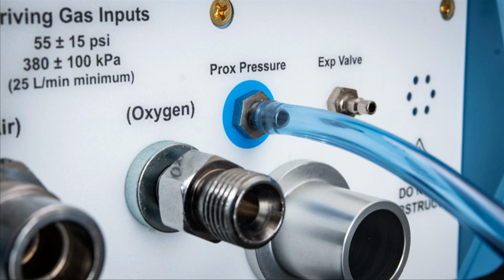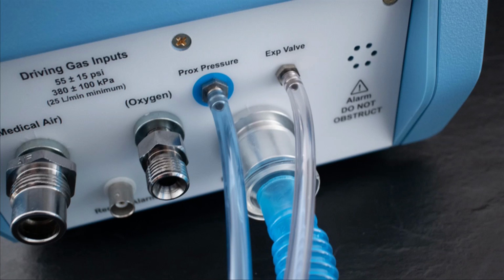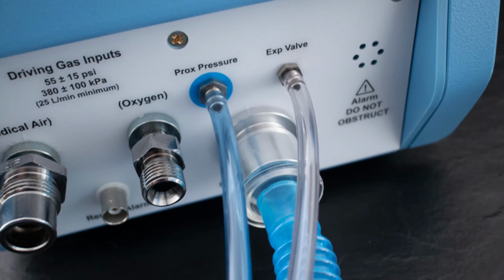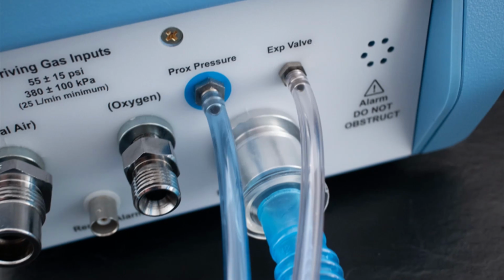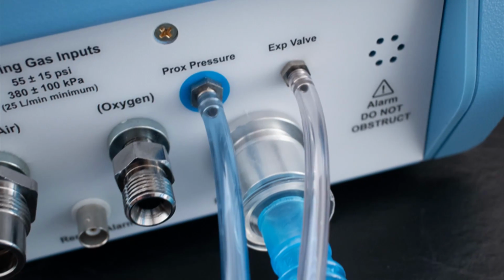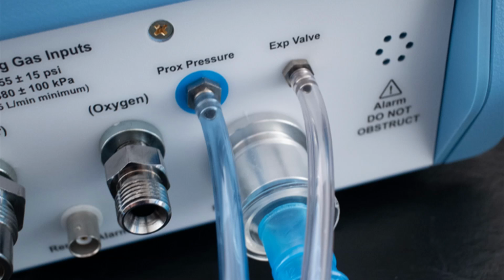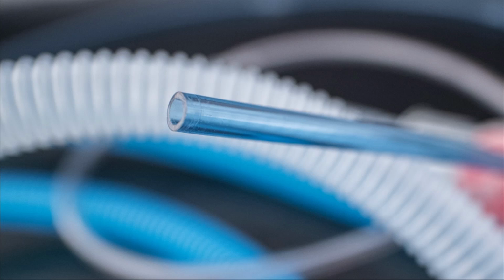You will note that the proximal pressure line is a 4 millimeter small blue tubing and will connect to the prox pressure barb connector, which is outlined with a blue circle. The proximal pressure line allows for the measurement and display of airway pressure at the patient circuit Y to enhance patient safety and monitoring of delivered pressure during ventilation. The proximal pressure line is easily distinguished from the expiratory valve tubing in color and size.